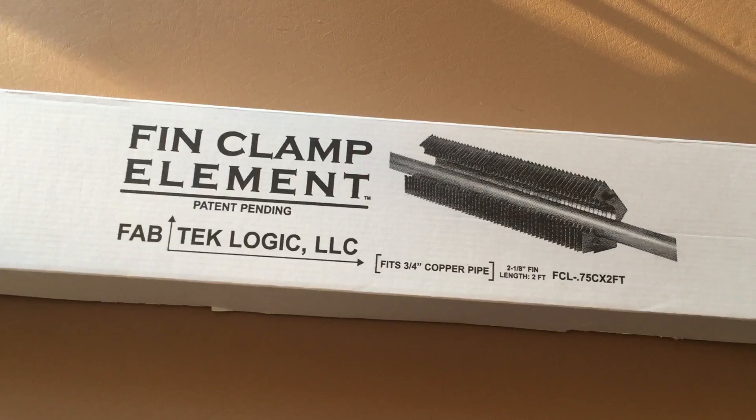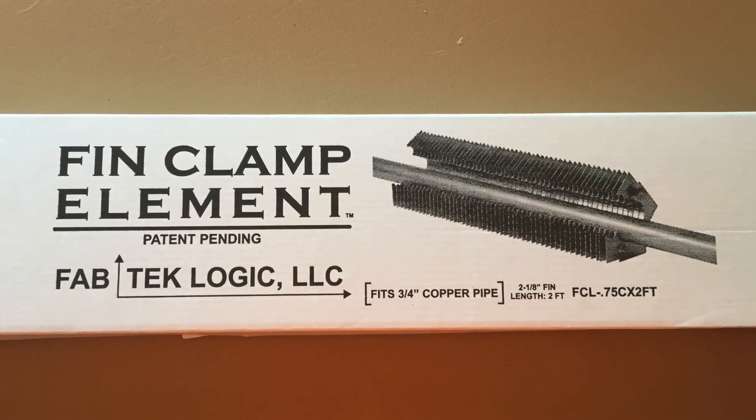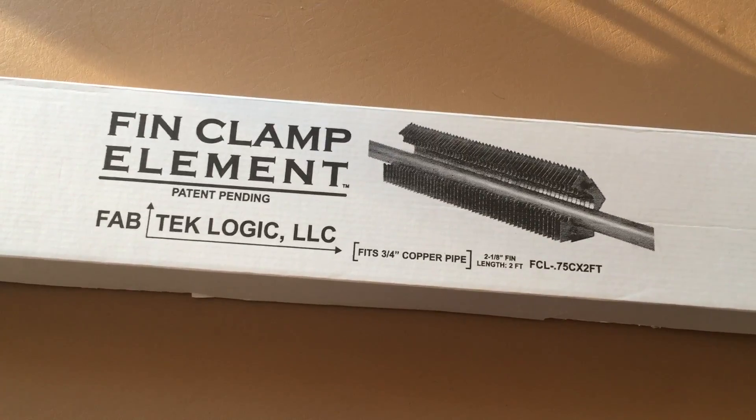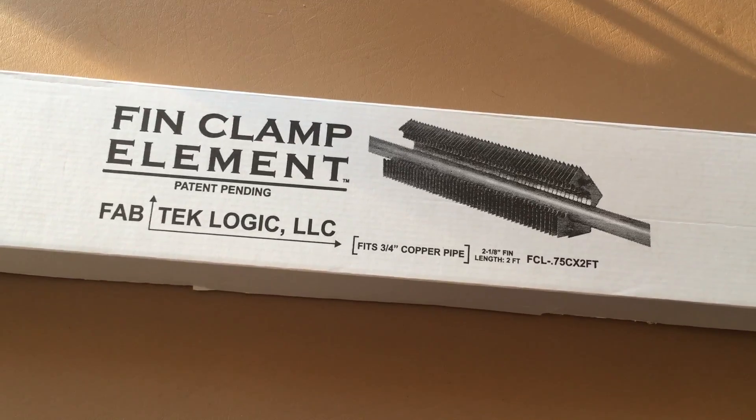So in the process of trying to figure out how to handle this and increase the efficiency of my boiler, I stumbled over a product. The product is called a fin clamp element and it's made by a company named Fab Tek Logic. It comes in a few different pipe diameter sizes and from what I could tell from the internet, it comes in one and two foot lengths.